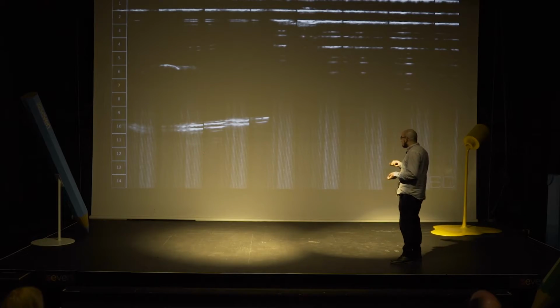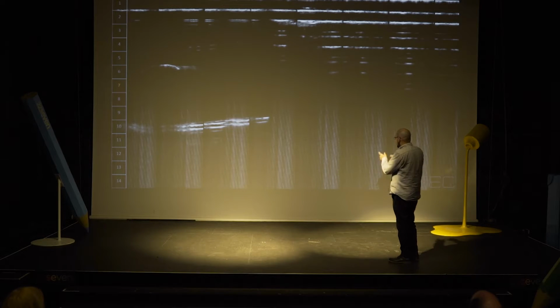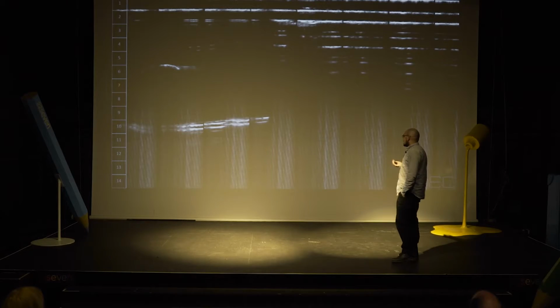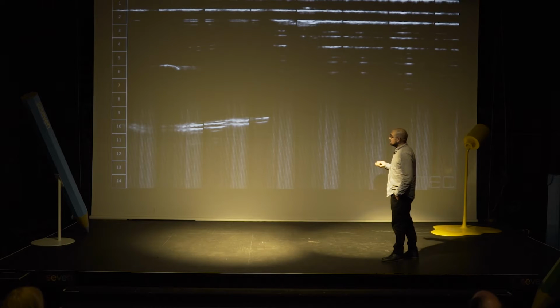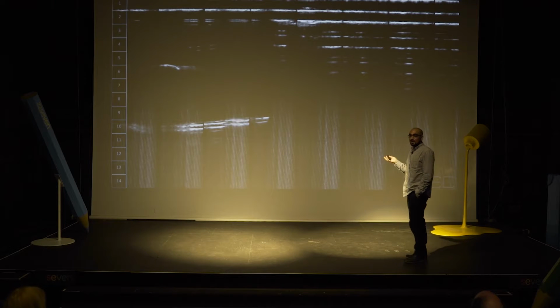And you can kind of see that, not so much from where you're standing, but there are 10 bands that have been stitched together here, which is the entire image. What that means is that it takes 10 times longer to acquire this ultrasound image than with a handheld ultrasound probe. And that's not really a good thing, because the compression paddle applies forces of up to 20 kilograms, and that's literally like putting a suitcase on your breast. So we obviously want to minimize that time.